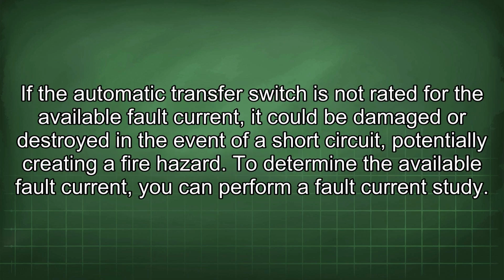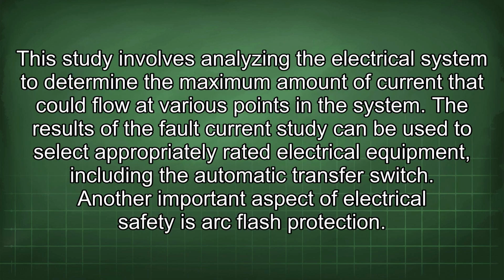If the automatic transfer switch is not rated for the available fault current, it could be damaged or destroyed in the event of a short circuit, potentially creating a fire hazard. To determine the available fault current, you can perform a fault current study. This study involves analyzing the electrical system to determine the maximum amount of current that could flow at various points in the system.